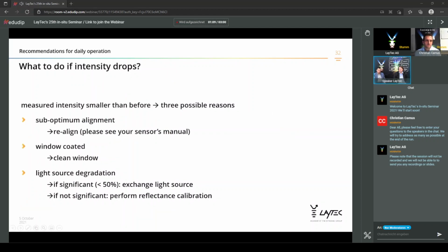Well, what to do if the intensity drops? Suboptimum alignment means you need to realign it. Please refer to the manual or contact LayTec, contact Aixtron, the tech support, or the LayTec service partner if you are in a region where we have our service partners. Well, if the window is coated, for different technologies, it was always a wet cleaning. So you have etched the viewport window in some kind of acid mixture. But I saw now also some dry cleaning methods. Both are possible. Heiko was just agreeing that dry cleaning is also possible.